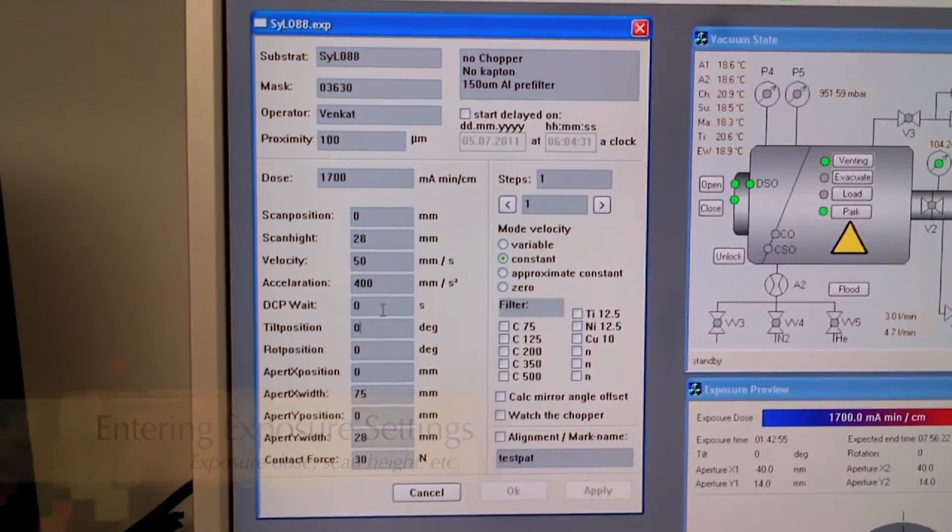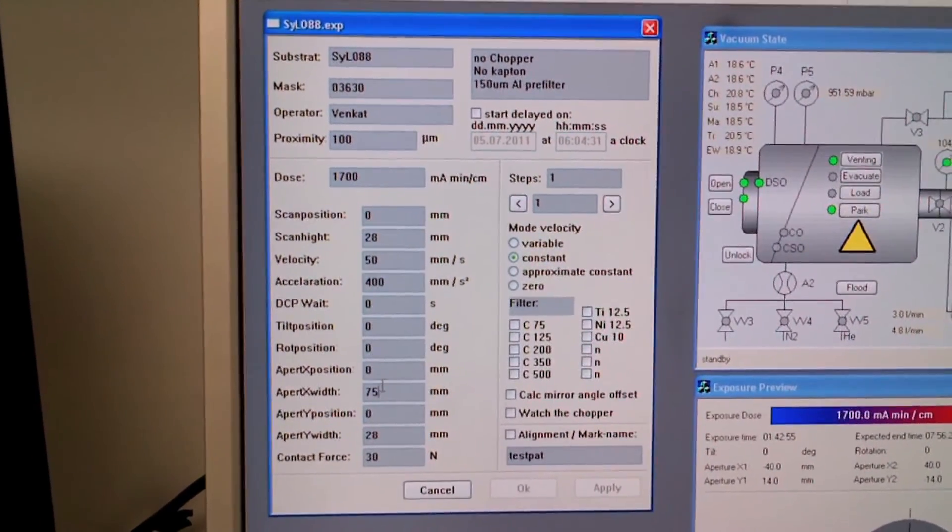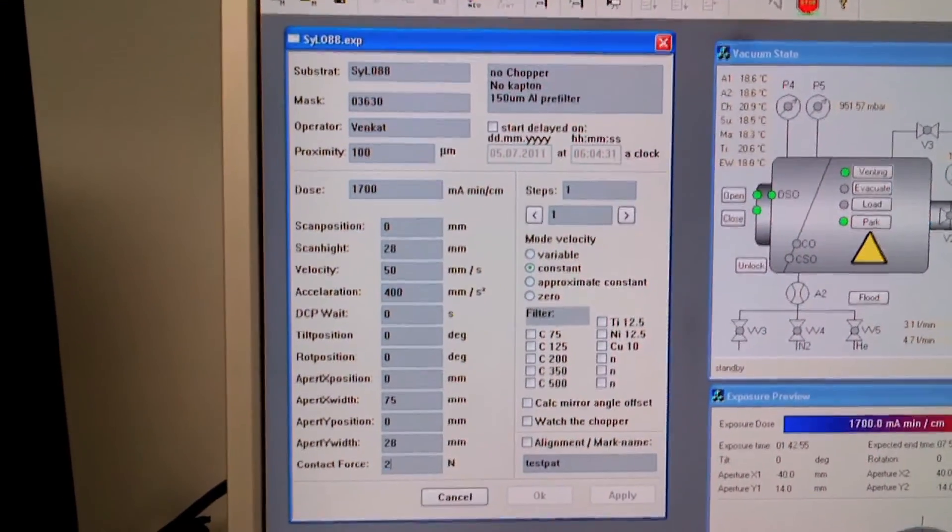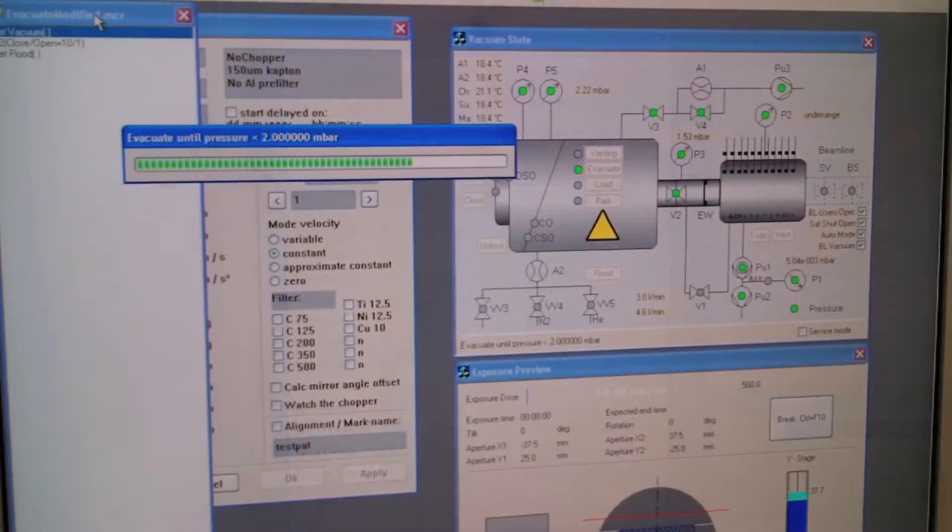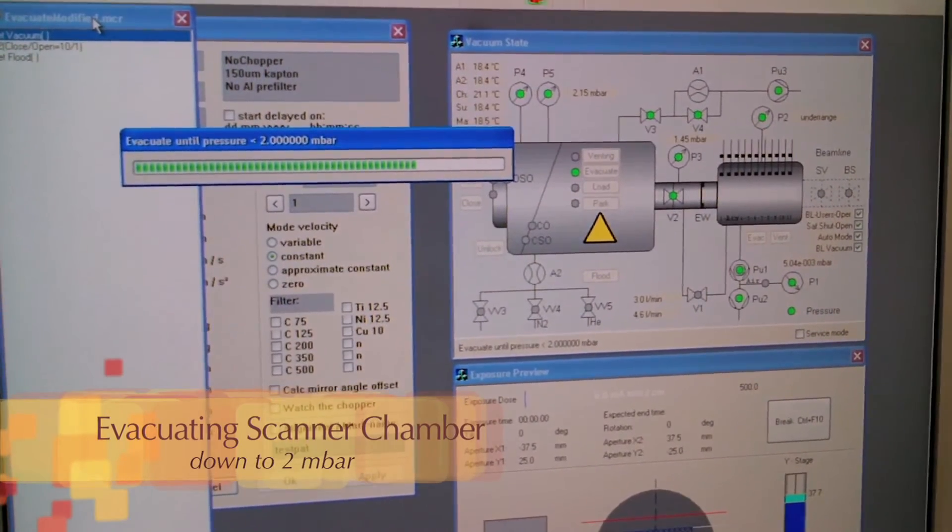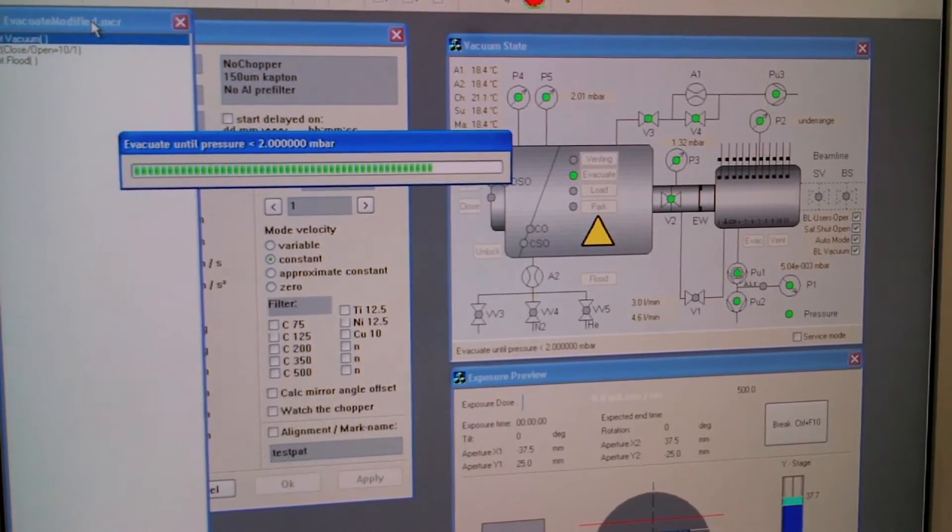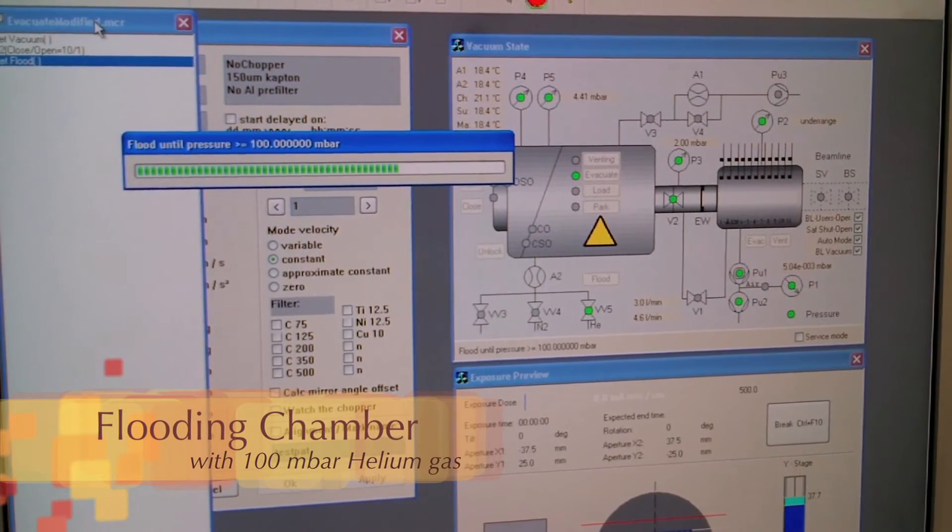In addition to exposure dose, this includes the scan height, scan speed, and the aperture settings to define the beam size, including the contact force to be applied to hold the mask and the sample together during the exposure scan. The exposure macro then goes through the initialization process and pumps down the scanner chamber to 2 millibar followed by flooding of the chamber with 100 millibar of helium.